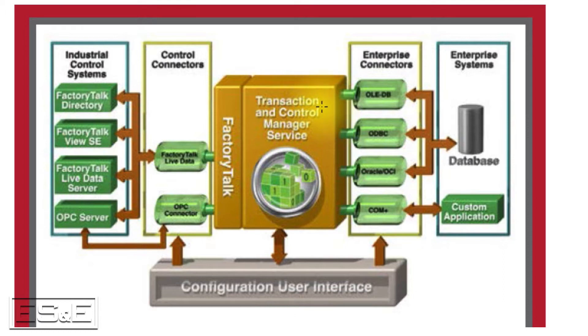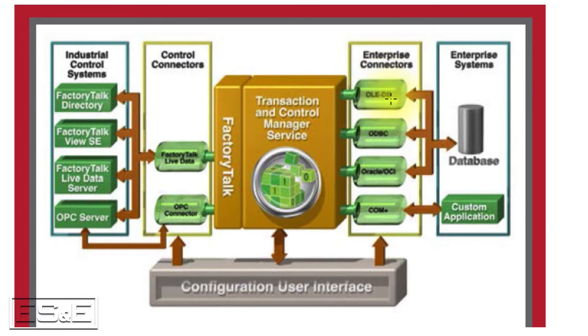One example we see used a lot is recipe management. If you want your recipes to be centrally stored and managed from an enterprise system, those recipes could be stored in a relational database. Via the SCADA or HMI, you would select which recipe you want to run, and that would trigger the database to send those values from the database table down to the controller. That bi-directional capability really comes in handy.